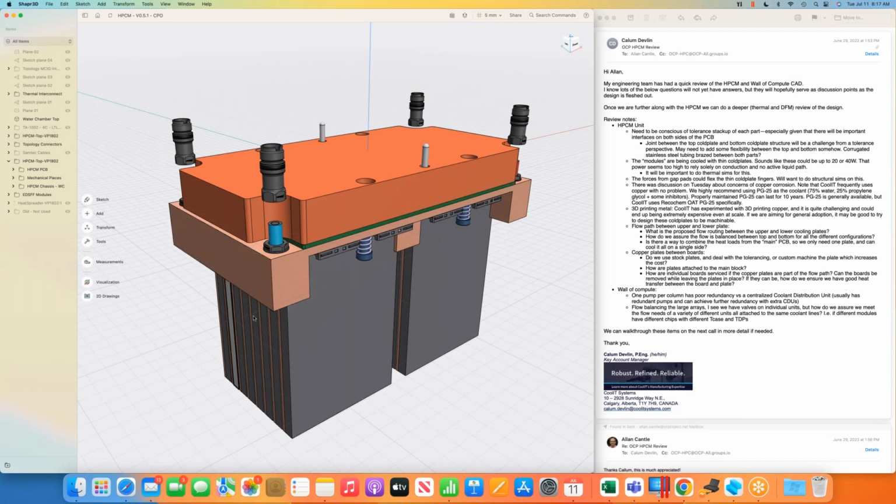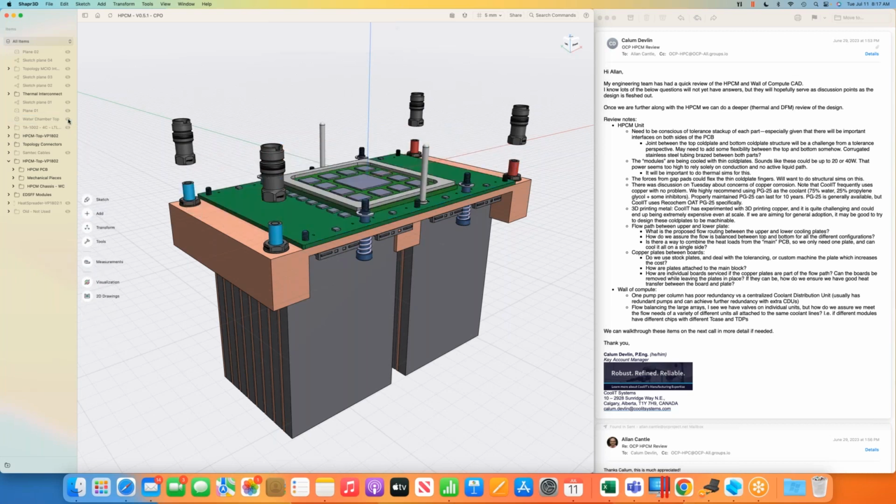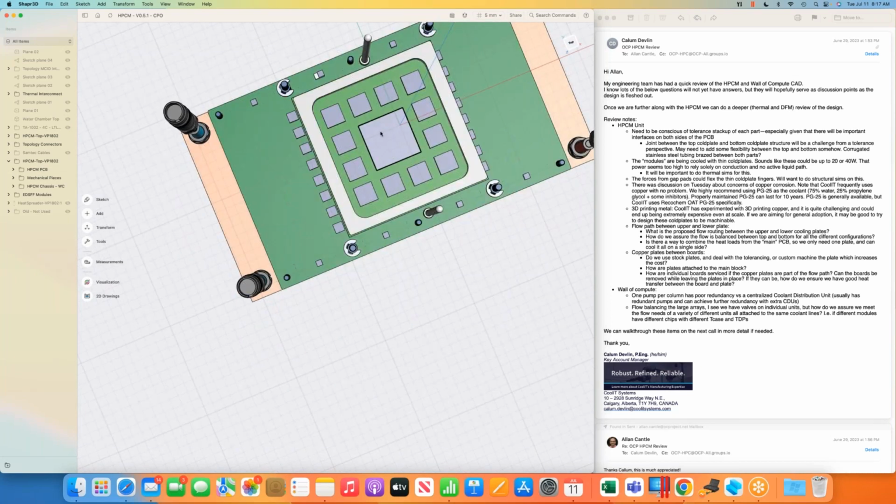No, these are the media modules. So these are E3.S as an example. These modules, there's 16 of them. And then under this lid here, the water chamber is where you'd have your main processor. So this is your 1 kilowatt GPU or CPU or FPGA or whatever, or switch. This can be a switch as well.